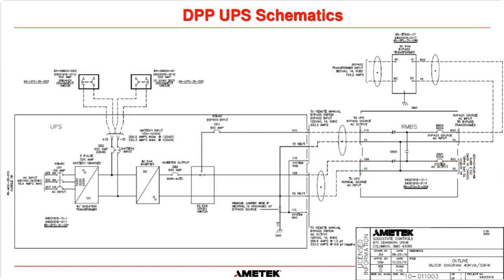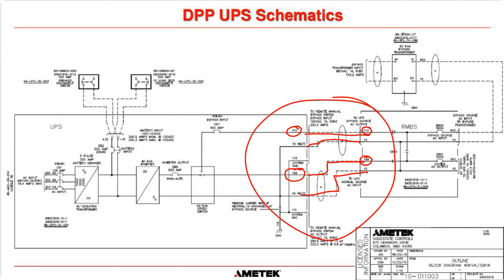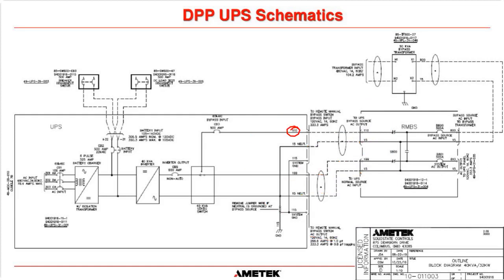But the real thing that I wanted to show you here is, because we're the manufacturer, we know what the cable numbers are going to be. So we always label our cable numbers so you can easily match them. This is terminal 110 in the RMBS, and this is terminal 110 in the UPS. As long as you match those terminals, you're good. Terminal 199 in the UPS, terminal 199 in the RMBS. Just connect those together and you will be good. Same with the 15s, connect them all to the neutral bars. So this side here is the most confusing thing for most people, but if you follow the wiring in both the UPS and the bypass switch, you can't go wrong.